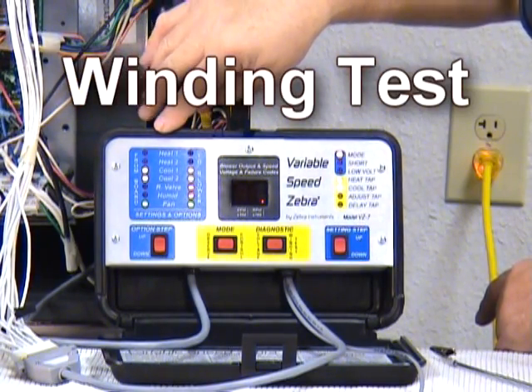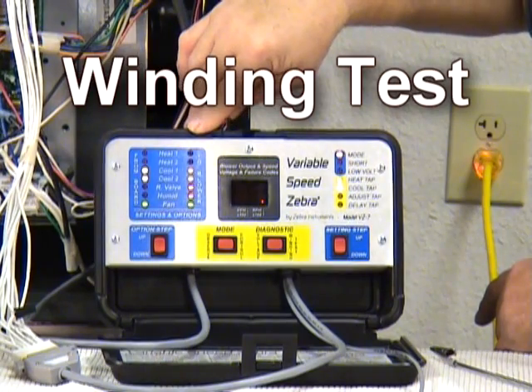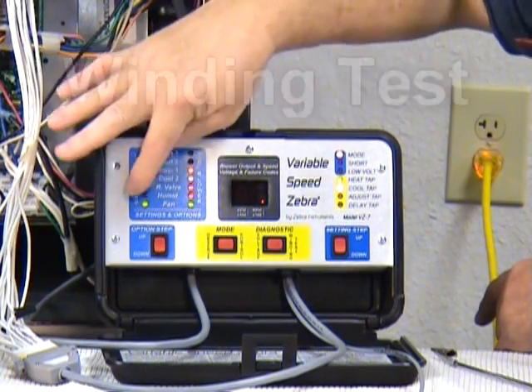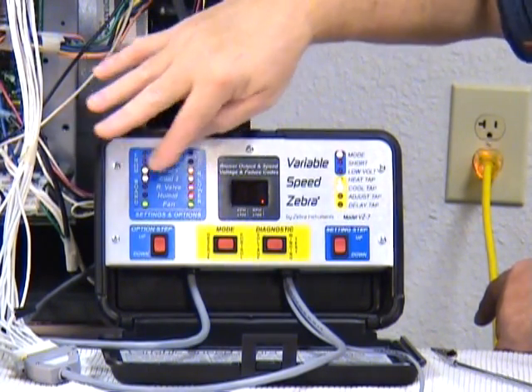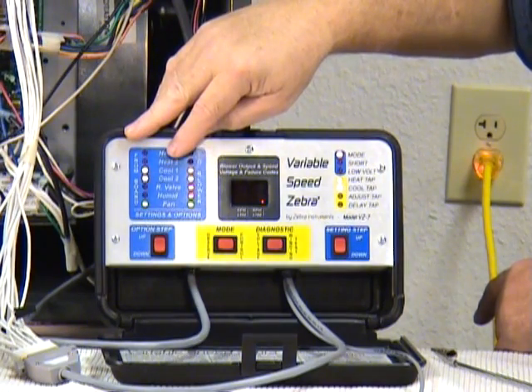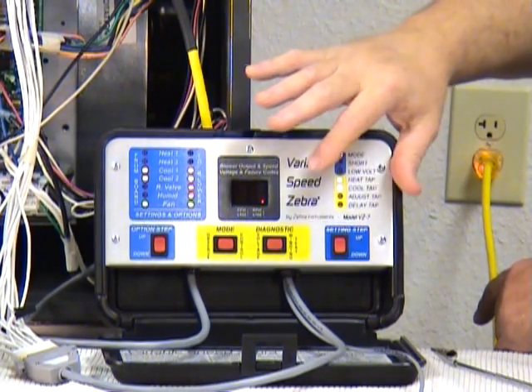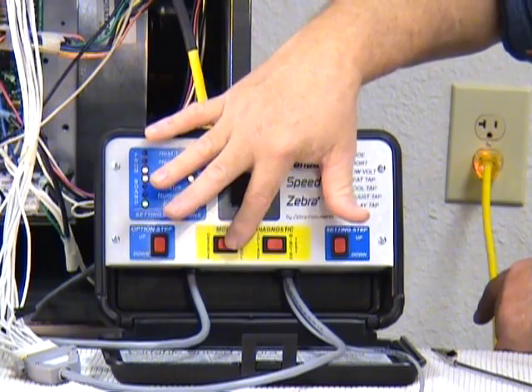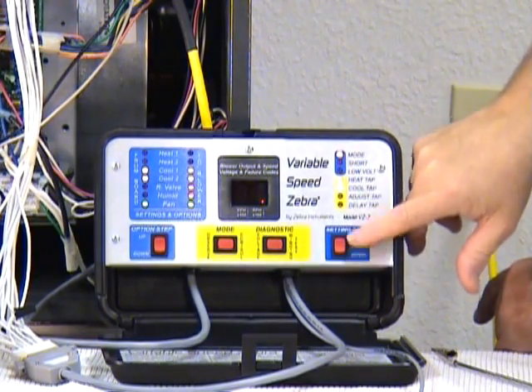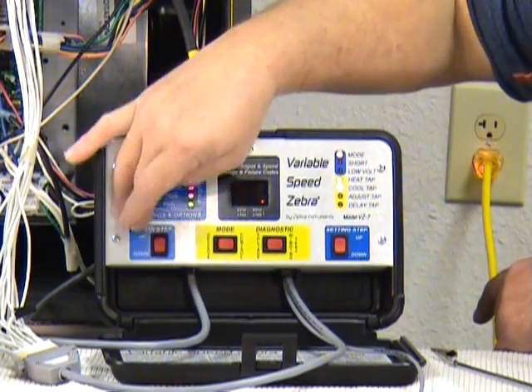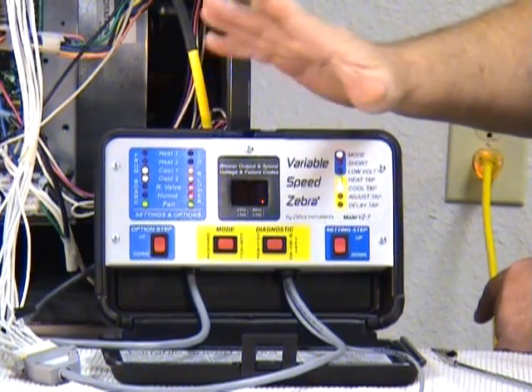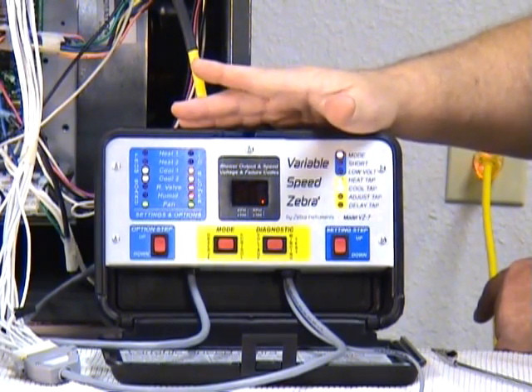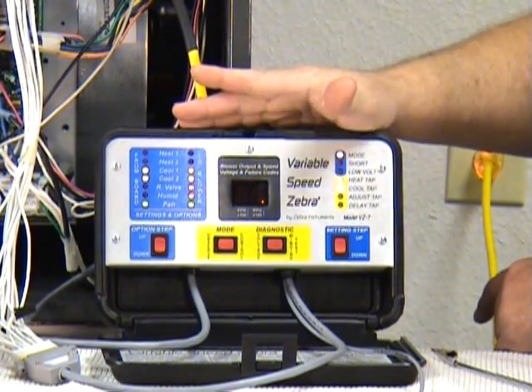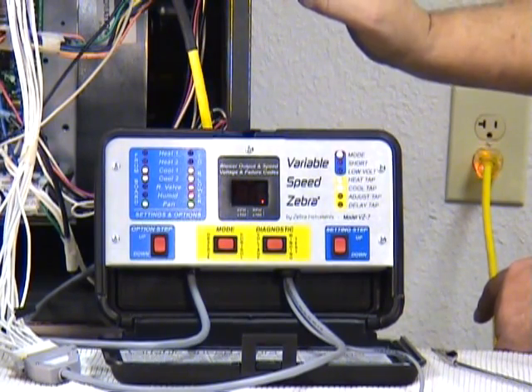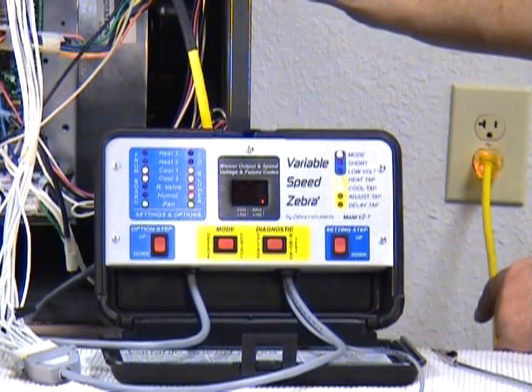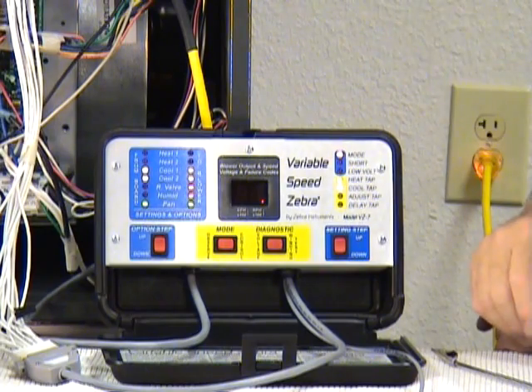So let's say that you've verified that there's power going into your motor. You've tried the observe mode and you've watched those signals going into the motor, but the motor doesn't work. And you've gone to the control mode and used your setting step switches and your option step switches to try a bunch of different motor speeds, and the motor just doesn't go, period. So because it's getting power and because it's getting signals, you know that the problem is somewhere in your motor.